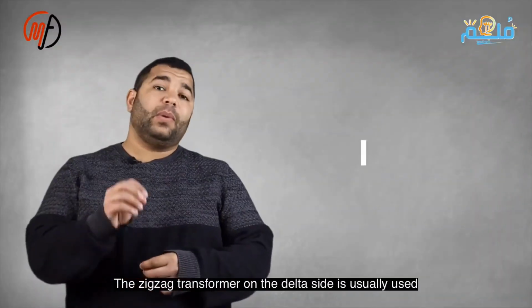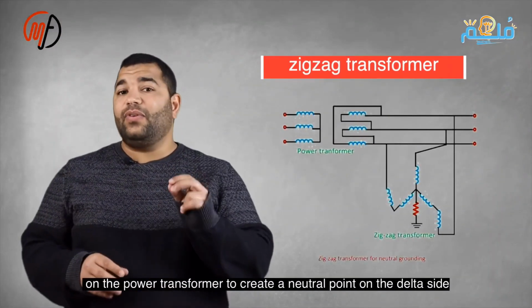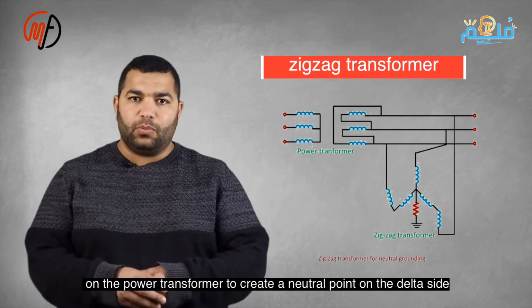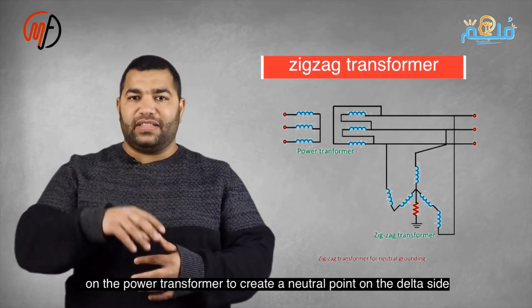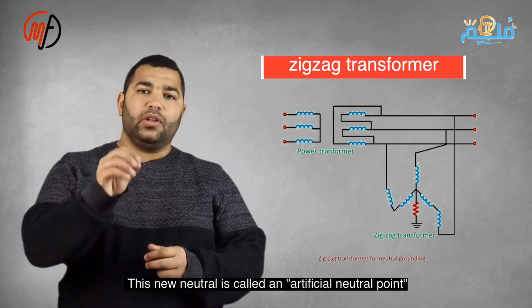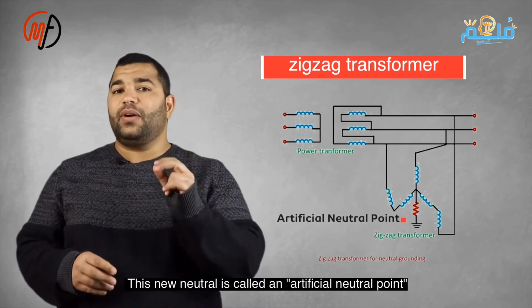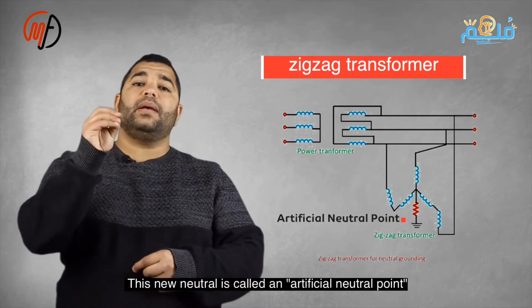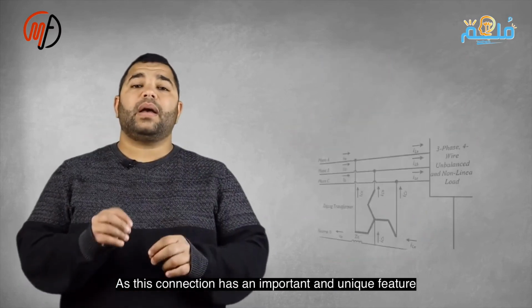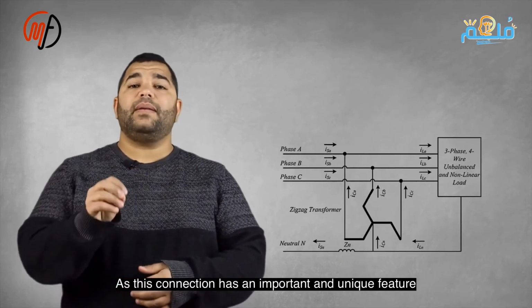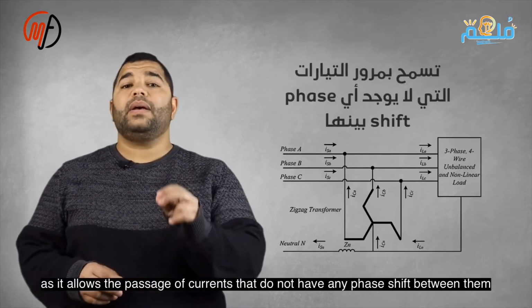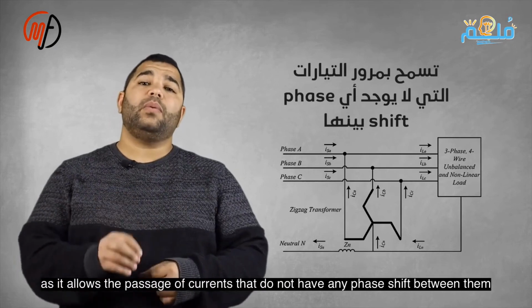The zigzag transformer is used on the delta side of a power transformer to create an artificial neutral point. This connection allows currents in phase to pass while blocking those with a 120-degree phase shift, serving as a grounding conductor for zero sequence currents. It's also known as the interconnected star and functions as a grounding transformer. The zigzag refers to its winding connection, and a CT can be placed on its neutral for standby earth fault.